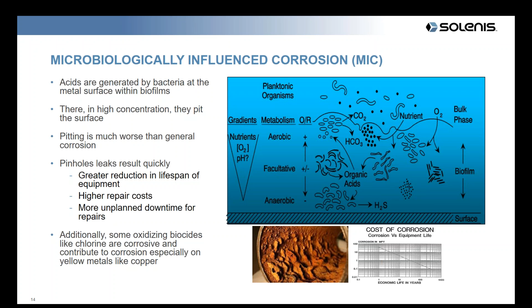And one pinhole leak is huge because you get unplanned downtime, or you have to do some sort of repair. Heaven forbid it's in your heat exchanger, or now you're dumping mash into your cooling tower, and now you've got an even bigger problem. And to top it off, your oxidizers may not be the most effective way of going after that, because the oxidizers themselves can lead to a more corrosive environment, especially with some of your systems that have yellow metals, like the tubes of your chiller.